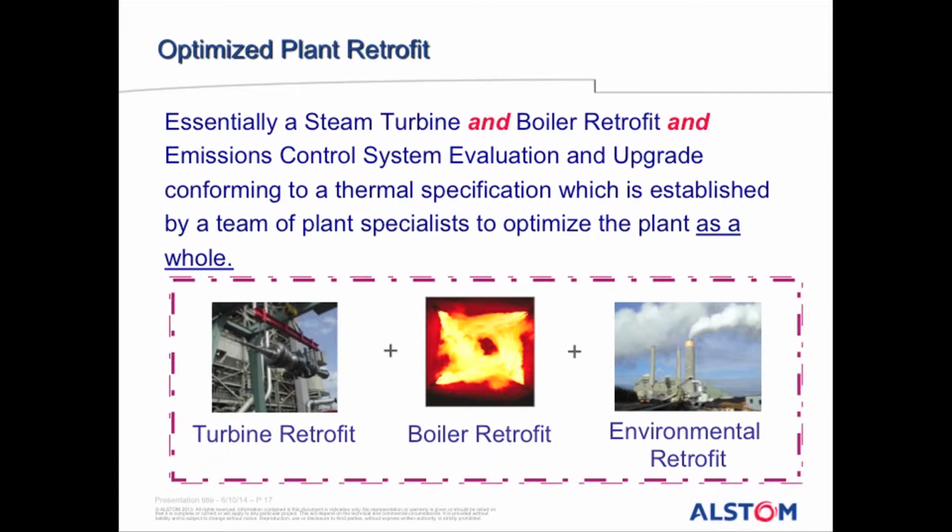One of the things, and I really didn't put it in the slides, but one of the biggest things that we're experiencing right now is electrostatic precipitators. There are relatively few fabric filters going in for MATS because we're finding upgrade of electronics with the improved TR sets and things can take an existing precipitator not only to the new levels, but to the levels that are going to be required under the PM NAAQS. So these are really important and cost-effective ways, because again, how do you tear down an electrostatic precipitator and build a fabric filter? We don't have the luxury in plants of building it one behind the other. So how do you accomplish this?